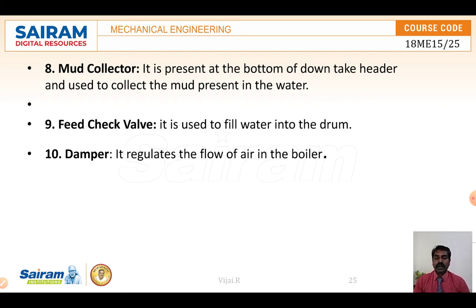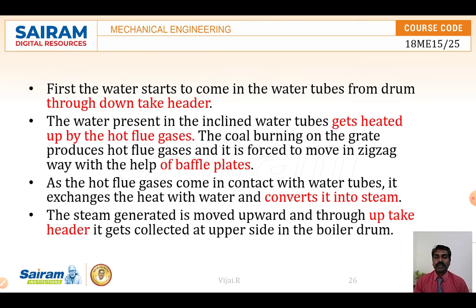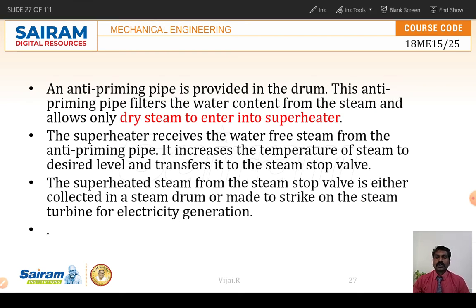Feed check valves control the water supply into the drum, ensuring the correct amount of water is maintained according to steam generation demand. Water comes through the downtake header, gets heated by hot flue gases contacting the water tubes, and converts into steam. Steam is generated upward, passes through the uptake header, and settles at the top of the drum. The dry steam then enters the superheater.